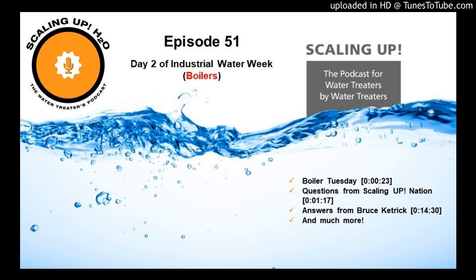Now, if you can look inside the boiler as water starts to boil, it breaks very easily at the top of the water surface. But when the concentration gets higher and higher, the water, when it boils, doesn't break as easily and it starts to build up. Those bubbles build up on each other and they form a foam, almost like shaving cream, if you will. Maybe not quite so thick, but they build up on each other and that can create a lot of issues. One of the issues that it will most likely cause is wet steam.